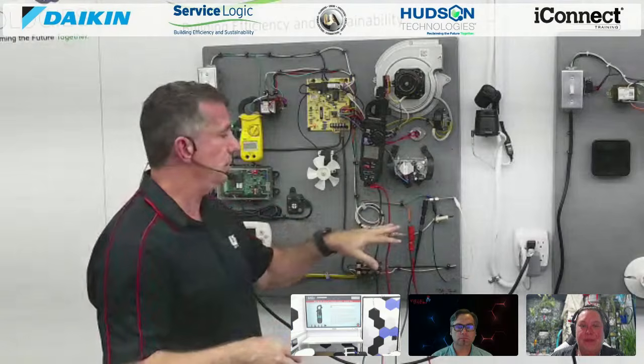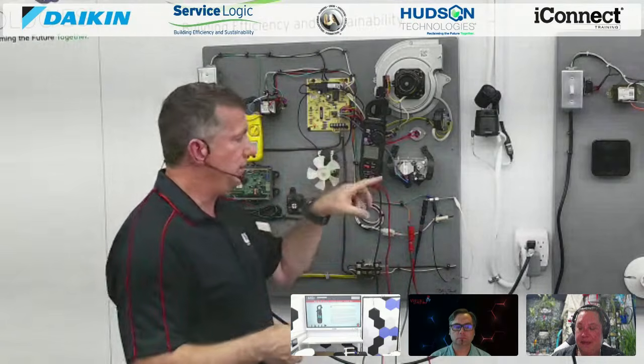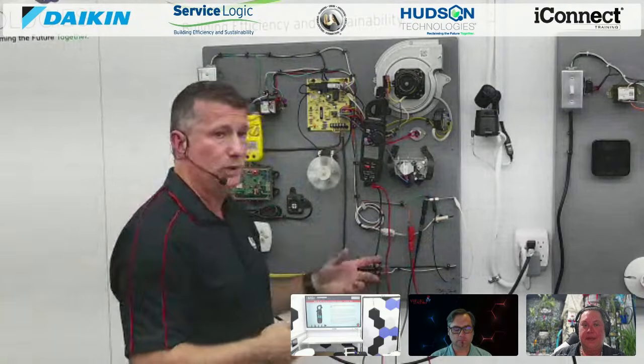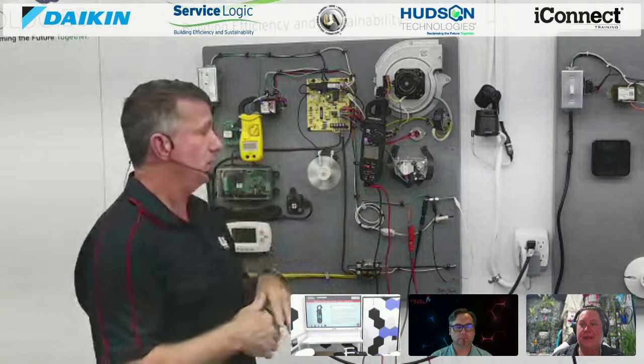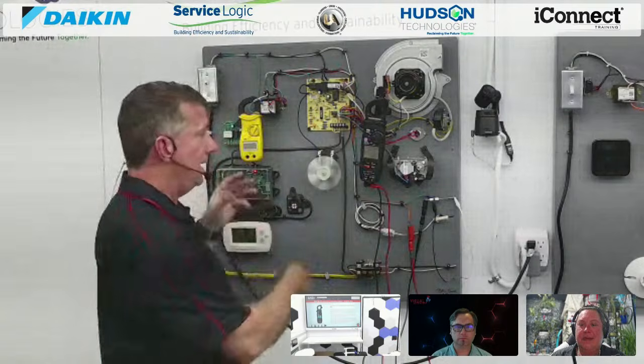We're wanting to make sure that we have sufficient flame rectification. Our AC is going to pass across the flame on its way to ground. As long as we have sufficient microamps, our circuit board is going to think it's just as happy as can be. And our control board thinks that it has flame right now.